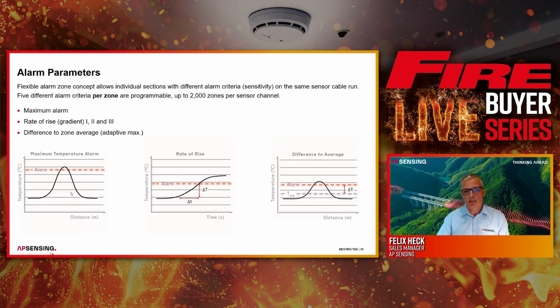This is the maximum temperature alarm, for example, at 60 degrees Celsius, the fire brigade will be called. Then we have 3 rate of rise criteria. If the temperature rises within a certain time, then the fire brigade will be called. Can be for slow smoldering fires or for very fast fires. For example, within 2 minutes, the temperature rises about 14 degrees Celsius. Then the fire brigade will be called. And we also have the difference to average zone alarm. If within a zone, the temperature rises to a certain value, 10 degrees, 15, 20, depends on the adjustment, then also the fire brigade will be called.